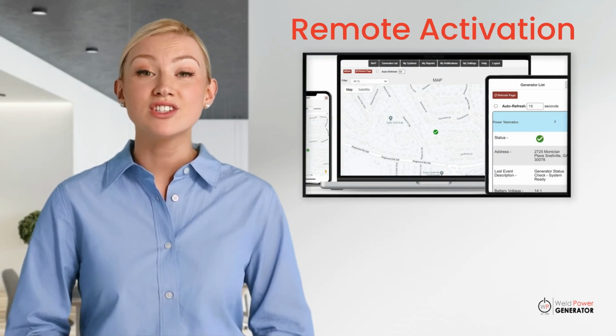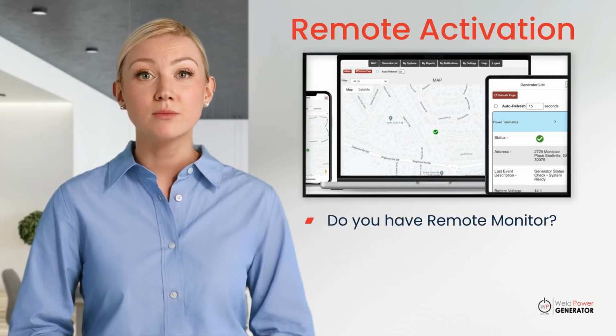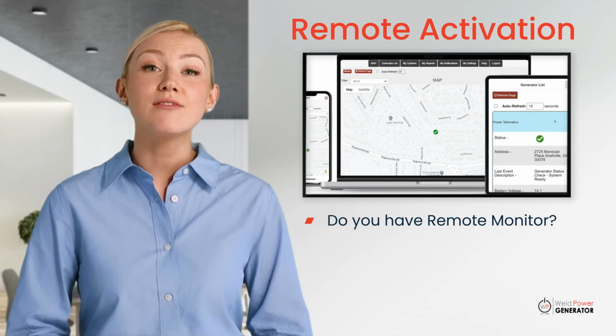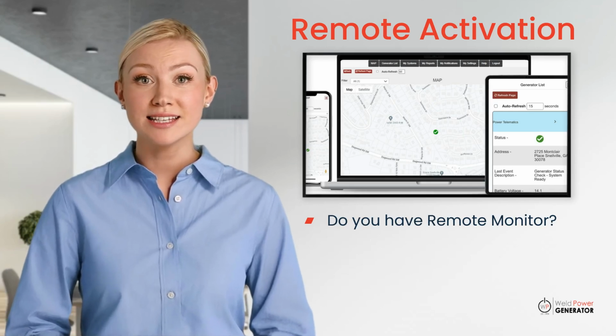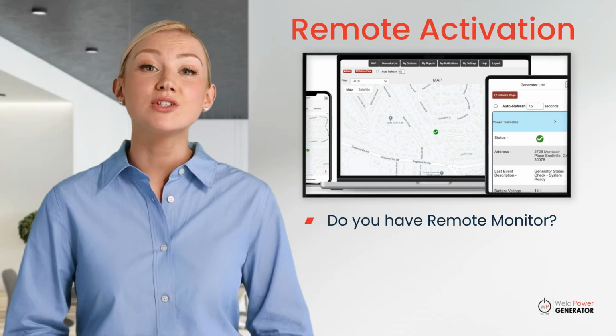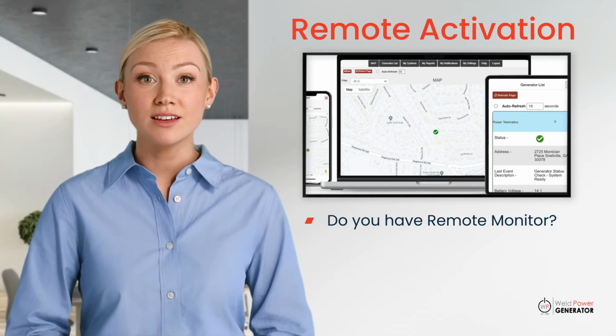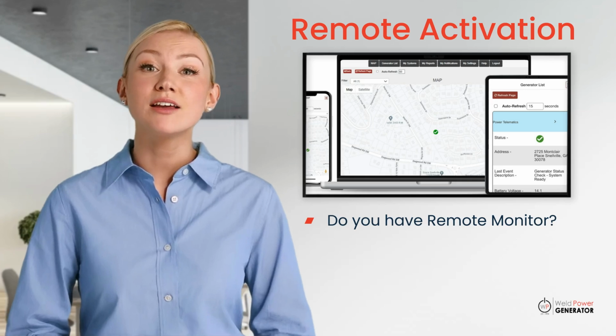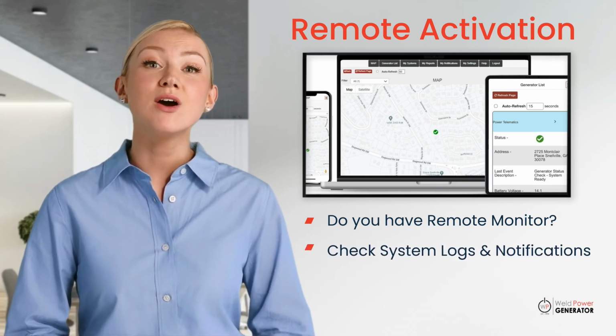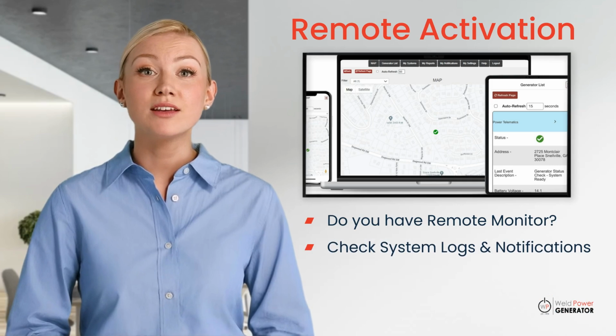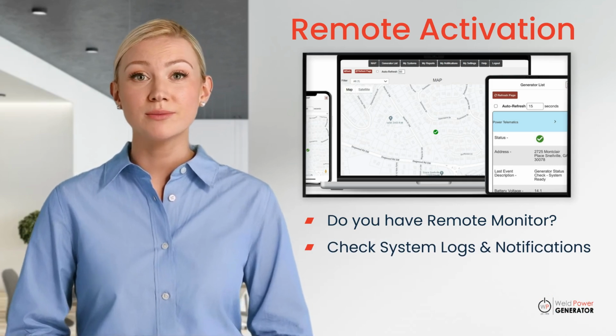Some generators are integrated into building management systems, BMS, or remote monitoring platforms that allow for remote start and testing. If an operator or technician remotely initiates a generator run, it may appear as if the unit is running for no reason. Checking system logs and notifications can help determine if a remote command was issued.